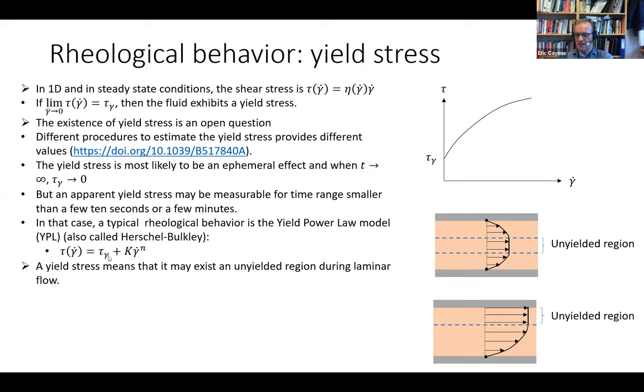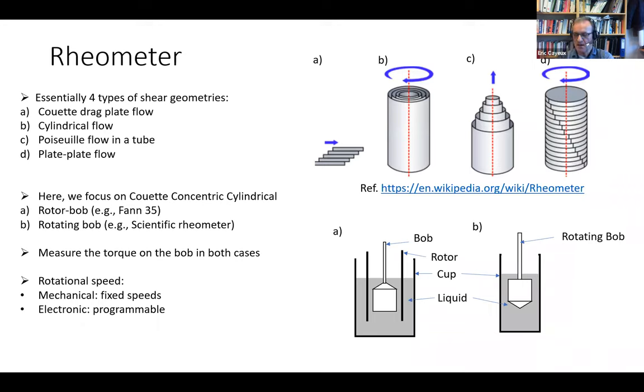The presence of yield stress means you may have a plug region in Poiseuille or Couette flow — an unyielded region. There are essentially four types of rheometers: Couette drag plate flow, cylindrical flow with rotating cylinders, Poiseuille flow tube, and plate flow with a rotating plate. In this presentation, we only focus on the Couette concentric cylindrical rheometer, configuration B — cylindrical flow.